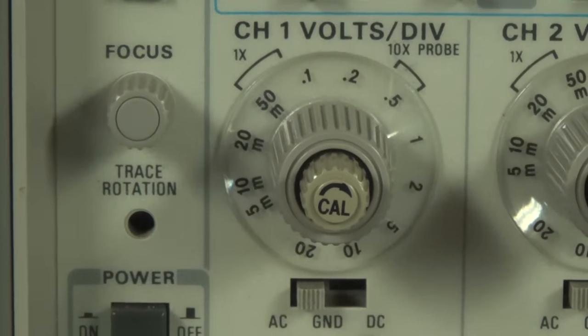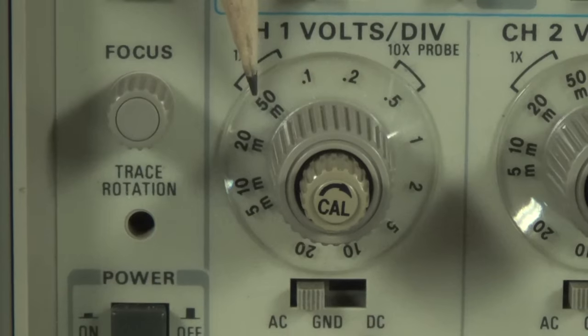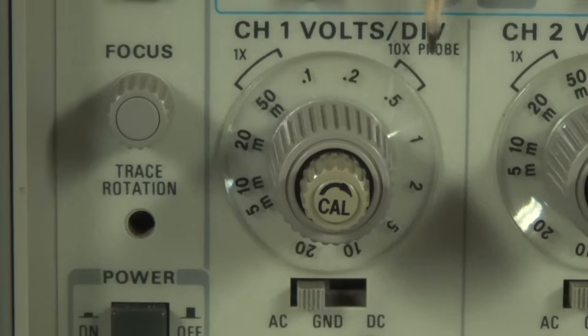Now I'm not sure if some of you noticed, but there is a shortcut. Instead of calculating one-tenth of the original 0.5 volts, we can simply use this indicator over here when we shift it to a 10x probe to get the voltage per vertical square deflection value. Okay, so you can divide by 10 and use this as your indicator, or not do any division and simply use the 10x probe indicator to dial in your 0.5 volt value.